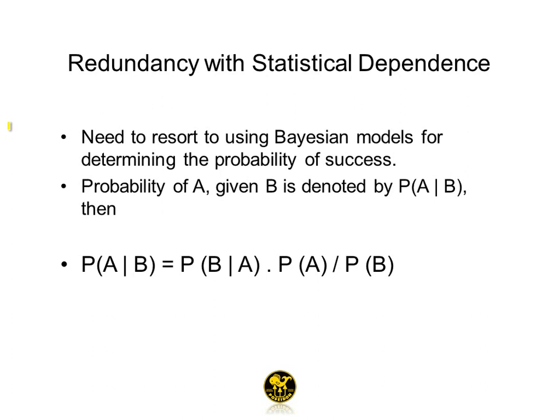So, what can we do about that? Well, there's something called Bayes' theorem in probability. It's related to conditional probability. What it comes down to is this. It says, what is the probability of X happening if Y has already happened? What that means is, if one oxygen sensor has already failed, is the probability that the second oxygen sensor has failed the same, greater, less, or whatever? So my friend Bayes here came up with this nice little equation that I won't bore you with the details on, but I'll just show you some of the results.